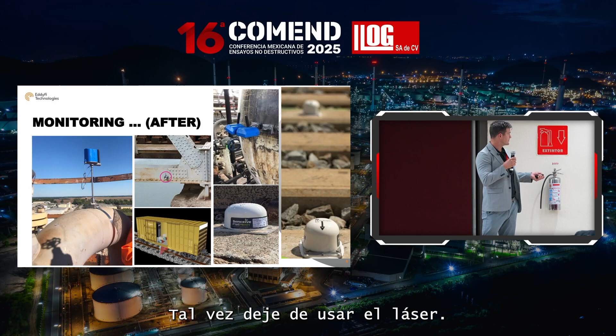They found this area of the pipe that had the most severe thinning and wall loss. Instead of sending someone into the field every day, week, or month to take a manual thickness reading to understand how fast it was corroding, the refinery - actually it was the inspection technician - said you don't need to send me out here every day. Why not put a sensor here that wakes up multiple times a day and takes a thickness reading, so you can plot thickness over time and understand how fast the asset is corroding. That's just one example of sensor technology.